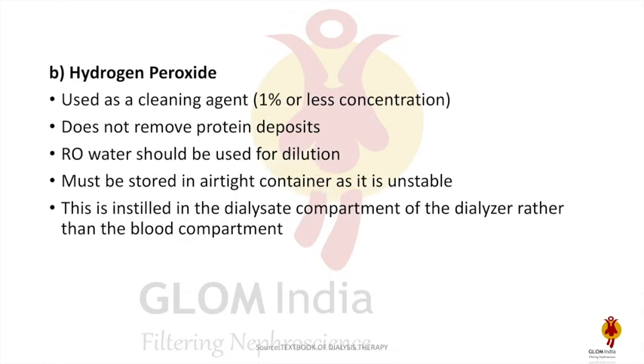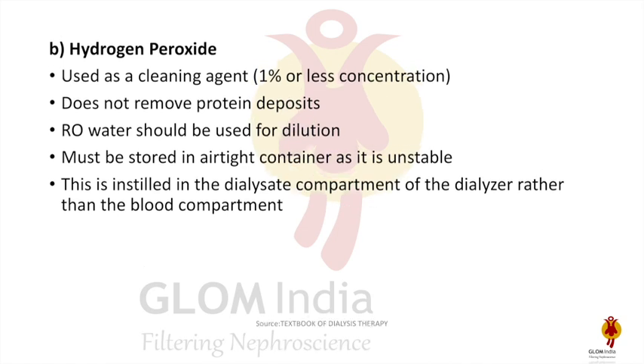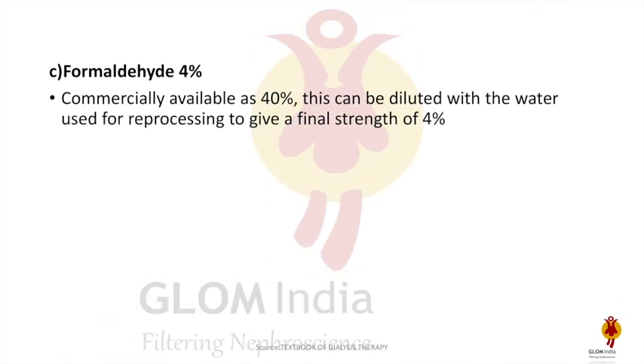The second agent is hydrogen peroxide, used as a cleaning agent generally at less than 1% concentration. It does not remove protein deposits. RO water should be used for its dilution. It must be stored in an airtight container as it is unstable, and it is to be instilled in the dialysate compartment — not in the blood compartment — because it can damage the blood compartment.